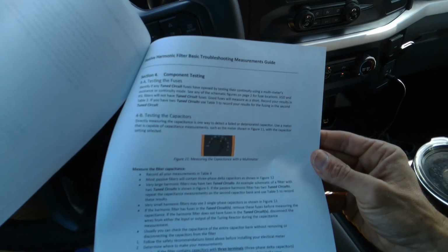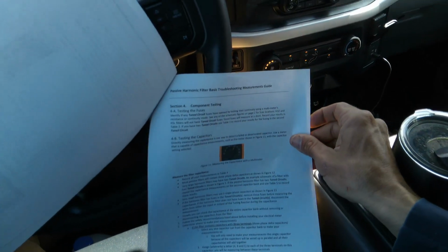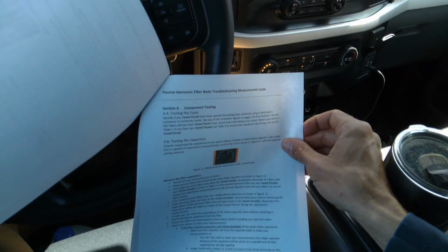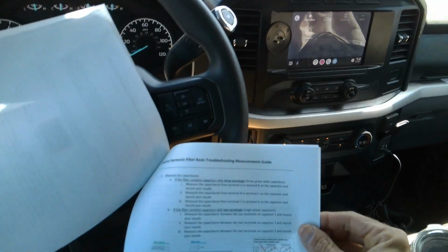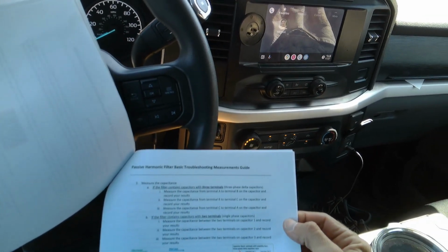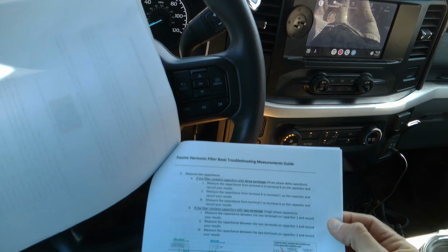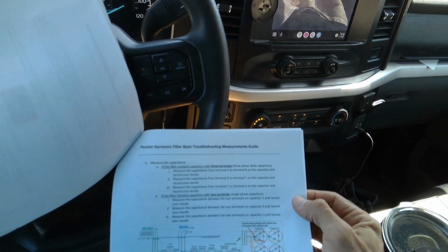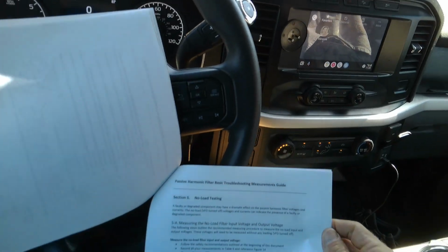If the filter contains capacitors of two terminals, those are single-phase capacitors. You'll need to measure the capacitance on each of the three cans. We'll go ahead and measure the capacitance. A to B, B to C, C to A. Good. No load testing.